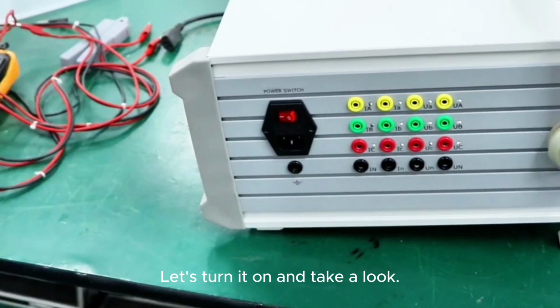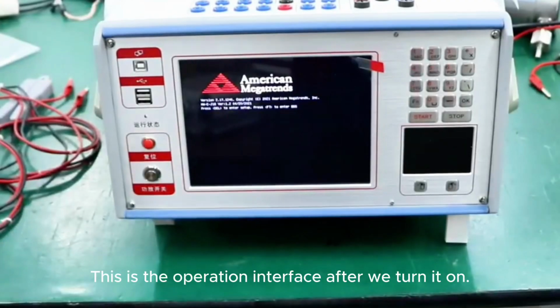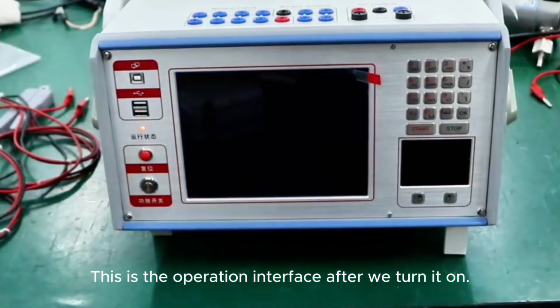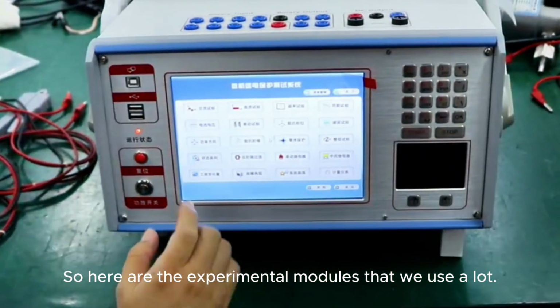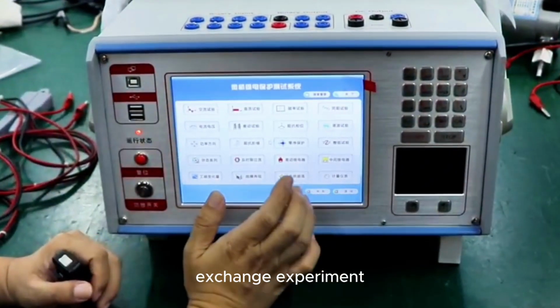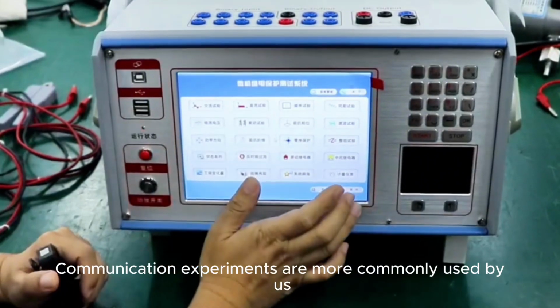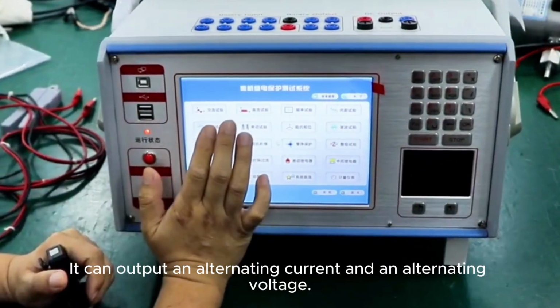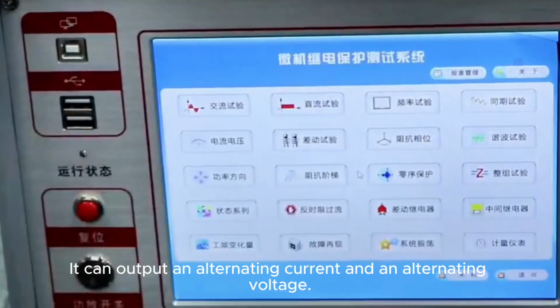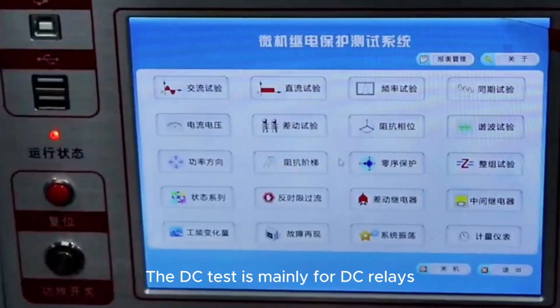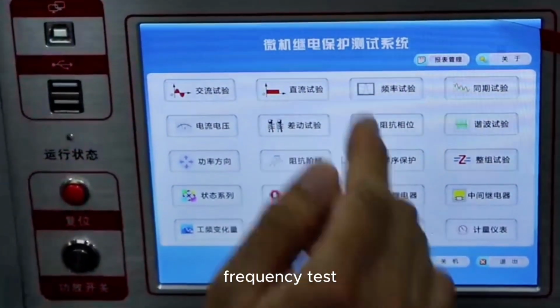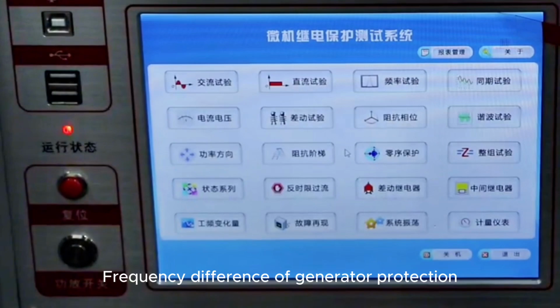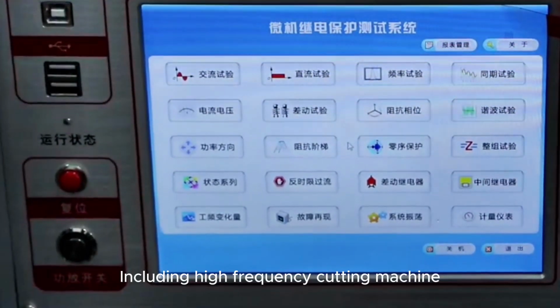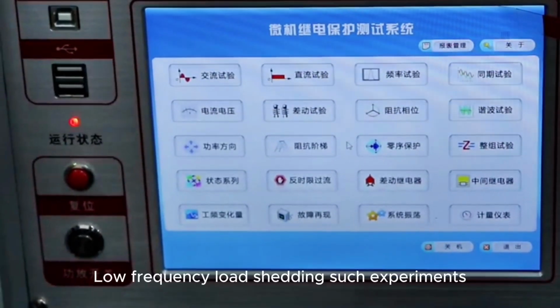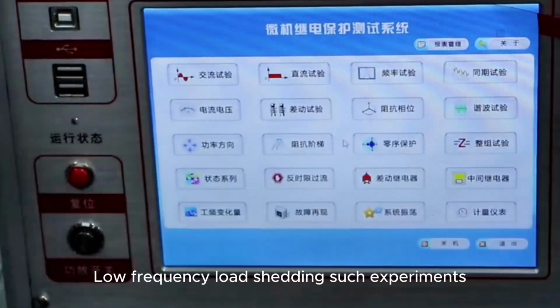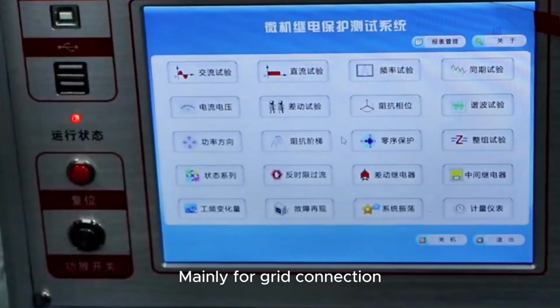Let's turn it on and take a look. This is the operation interface after we turn it on. So here are the experimental modules that we use a lot. AC test. AC experiments are more commonly used by us. It can now put out an alternating current and an alternating voltage. The DC test is mainly for DC relays. Frequency test. Mainly for frequency difference of generator protection, including high-frequency generator cutting. Low-frequency load shedding. Such experiments. Synchronization test, mainly for grid connection.